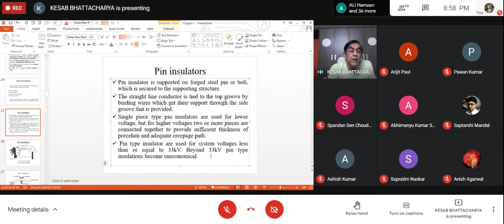Now another point: single piece type pin insulators are often used for lower voltage, but for higher voltage, two or more pieces are connected together to provide sufficient thickness of the porcelain and adequate creepage path. Pin type insulators are used for system voltages less than or equal to 33 kV. Beyond 33 kV, pin insulators become uneconomical. Why it becomes uneconomical, and what is the remedy, we shall discuss when we discuss suspension type of insulators. Now let us see the diagram of the pin insulators in the next slide.